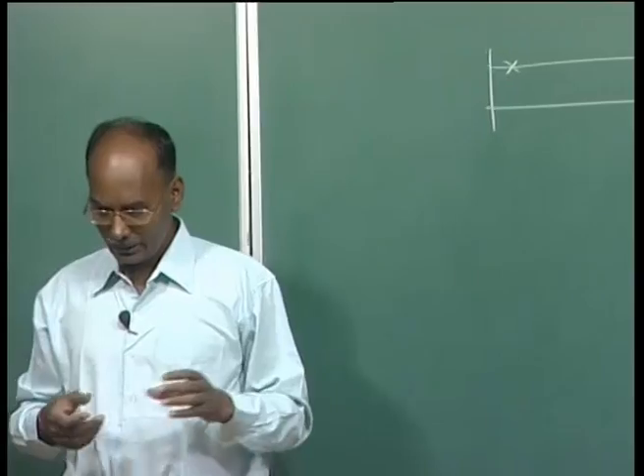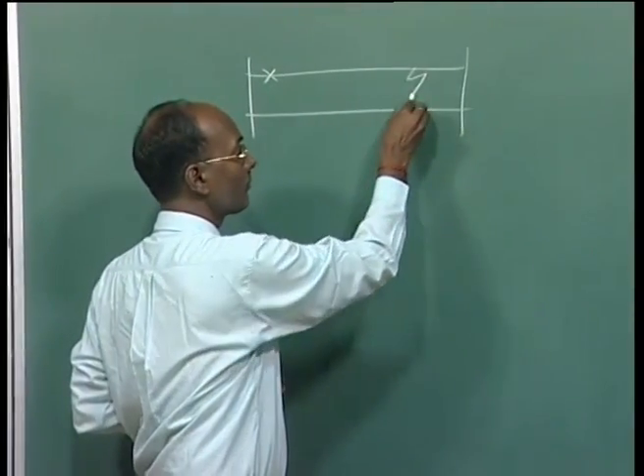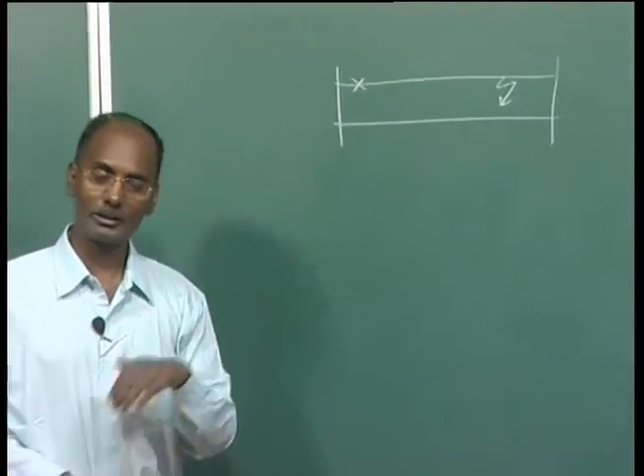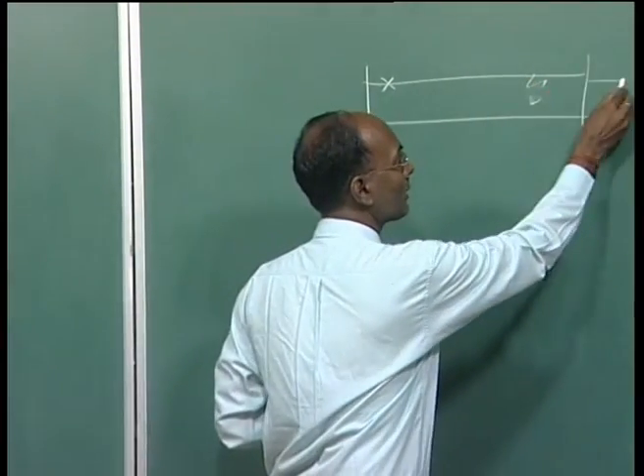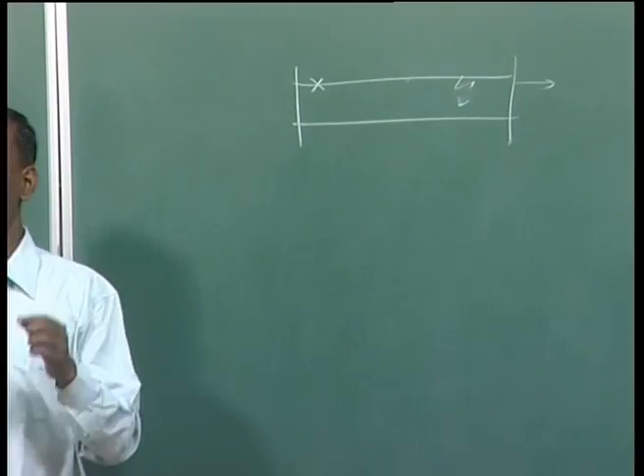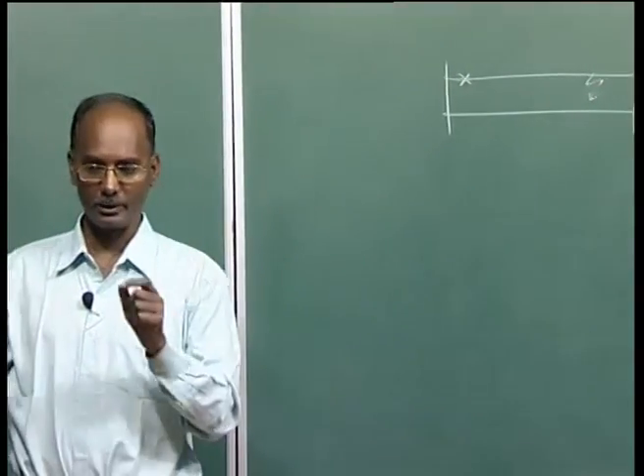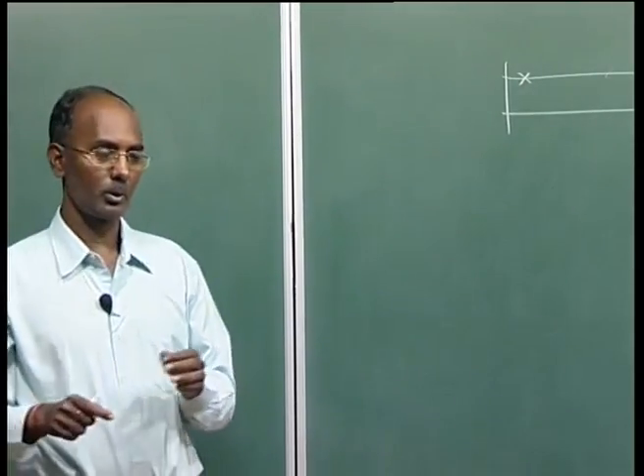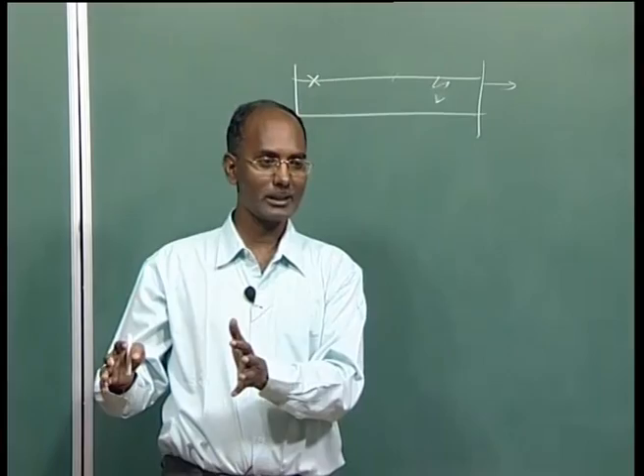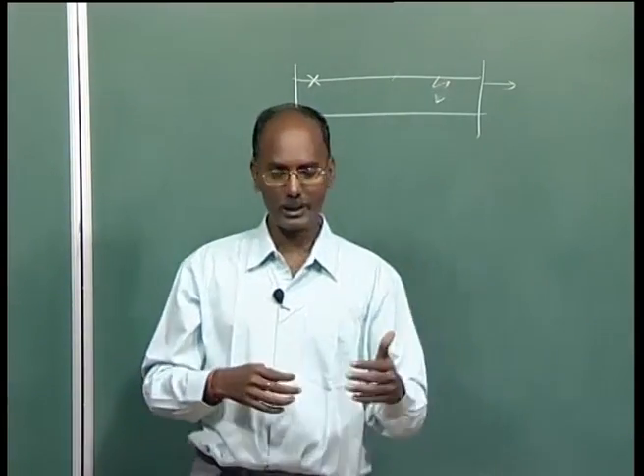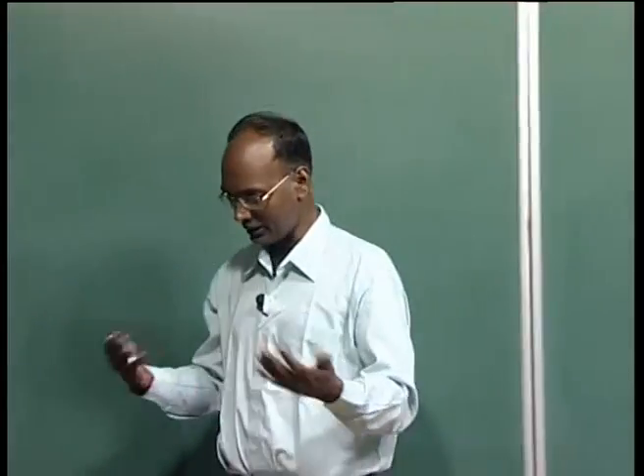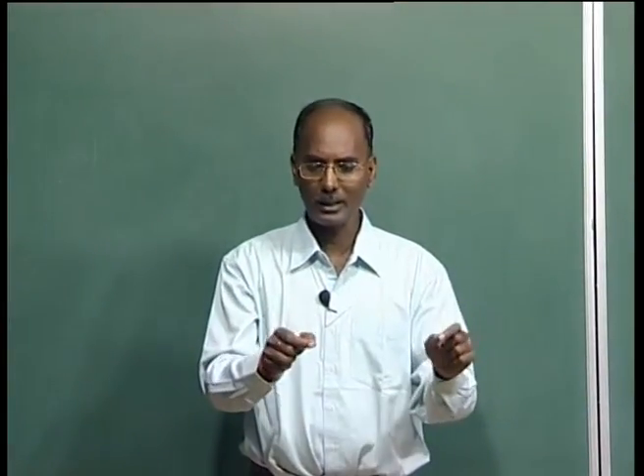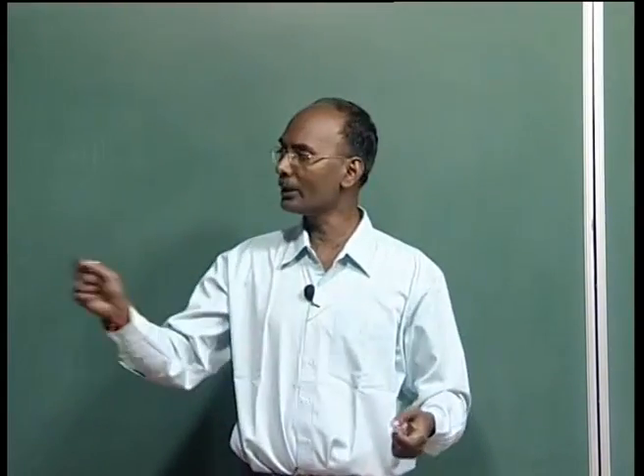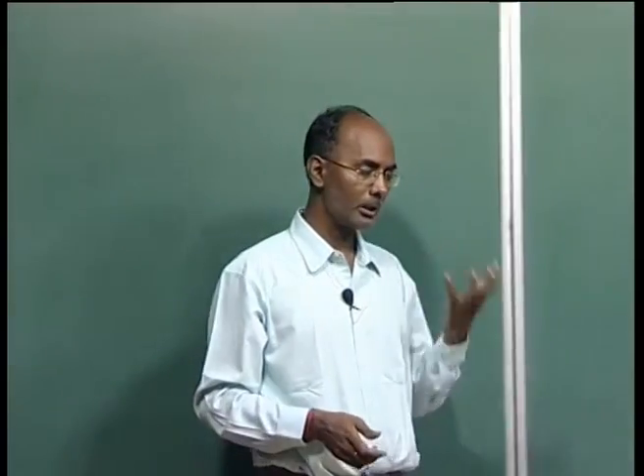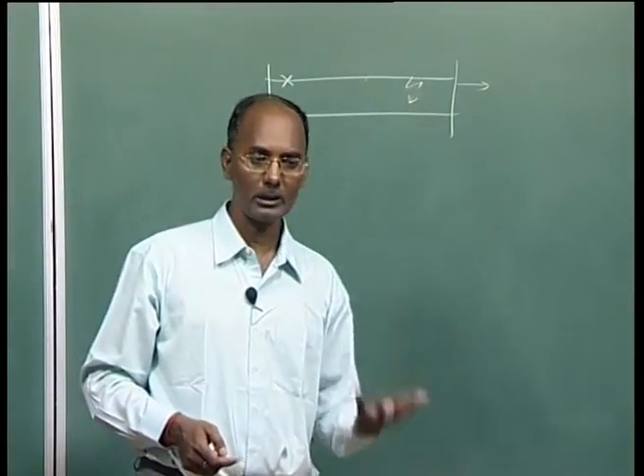Another is discriminative. Let's suppose there is some fault here. The current in this line will increase. There is also the possibility that, due to overloading, there is no fault but the current is increased. So the relay should clearly discriminate whether there is a fault or an overload. A relay should discriminate between the faulty condition and the healthy condition. In a healthy condition there may be a disturbance, maybe the current is higher. Your overcurrent relay should not operate for the overloading; it should operate only once the fault is there. So the relay should clearly discriminate whether there is a fault or not.